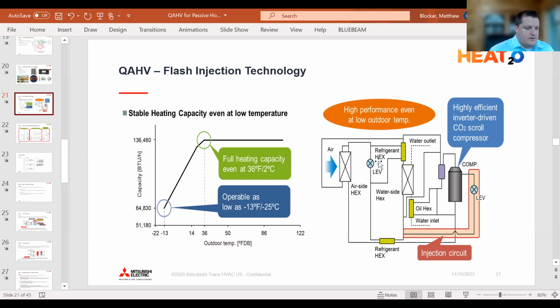It essentially will open up some different LEVs and close different LEVs that would act kind of similarly to a reversing valve. There is no reversing valve in it, and basically sends that hot gas right to the outdoor coil, and then comes back to the compressor. So very similar if you've looked at partial defrost or hot gas defrost in a VRF system.